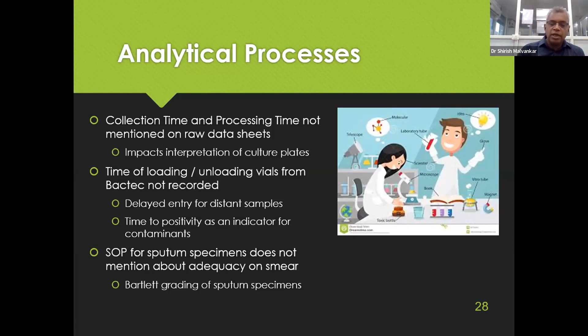Your SOP for sputum specimen sometimes does not mention adequacy on smear. And as we know, the Bartlett grading of sputum specimens is necessary to know whether your sputum sample has been adequate, whether your sputum sample is appropriate for testing or there has been a lot of salivary contamination in the sample, in which case you need to ask for a repeat sample after giving proper instruction to the laboratory or at the collection point. Only samples with a Bartlett grade of 1+ or more should ideally be processed further, or they are good for interpretation when you are interpreting your culture.